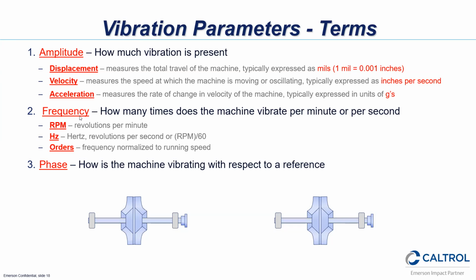Frequency is the time. So we take amplitude versus time that we're looking at RPMs. We measure everything in CPMs, which is relative to RPM. It's cycles per minute. So basically it reads the same as the RPM. If any of you are familiar with vibration analysis, a lot of technicians use Hertz. It's a lower number. It's basically the CPM divided by 60, and that's how you come up with Hertz if you're using that terminology. And then orders is the number of revolutions, or orders, of how fast the unit is running. So one order would be at speed. 2 orders would be at 2 times the speed of the fan, or whatever the machine is that you're testing.